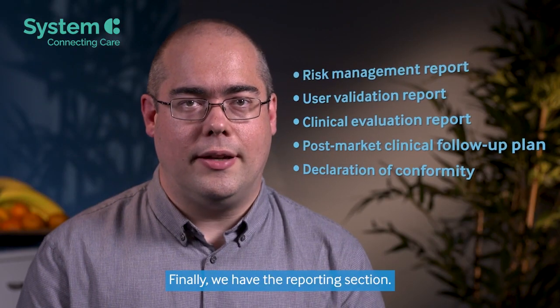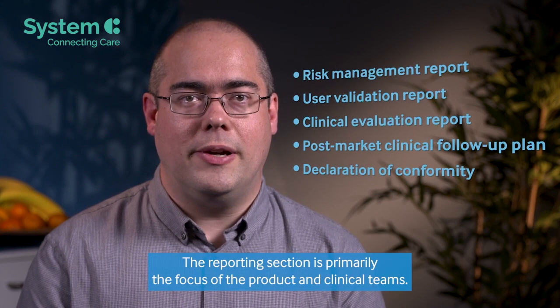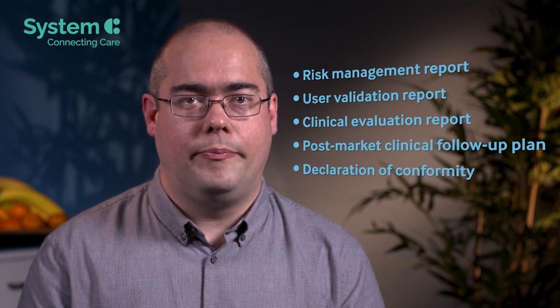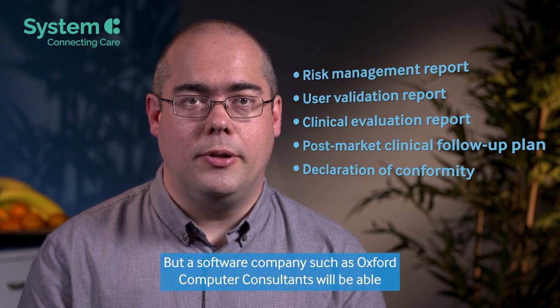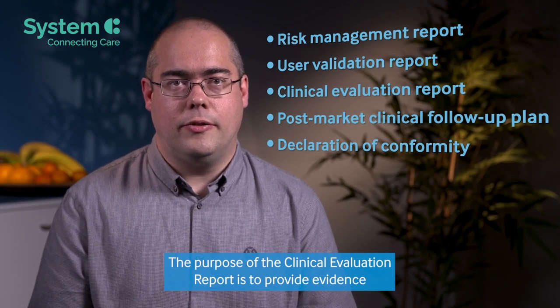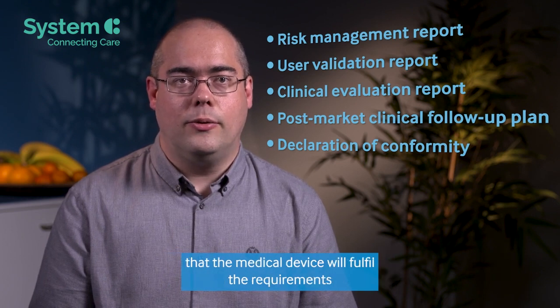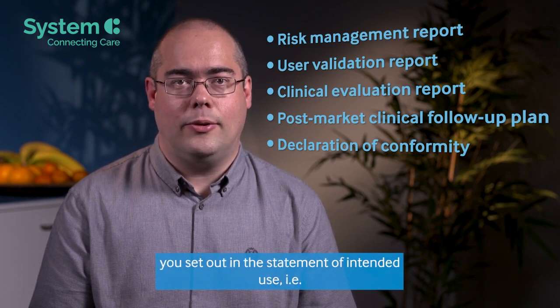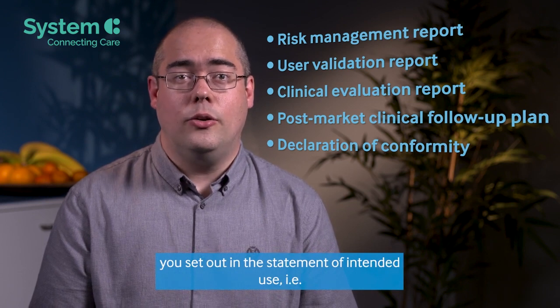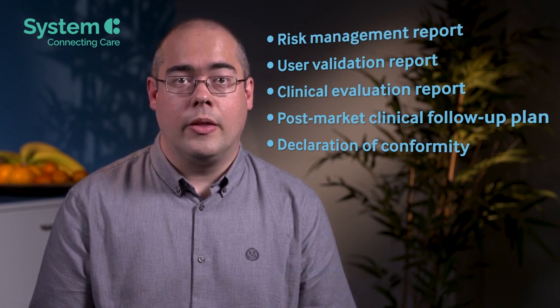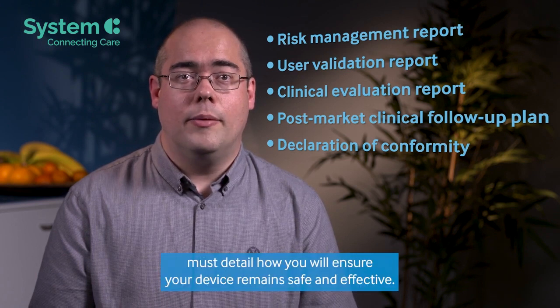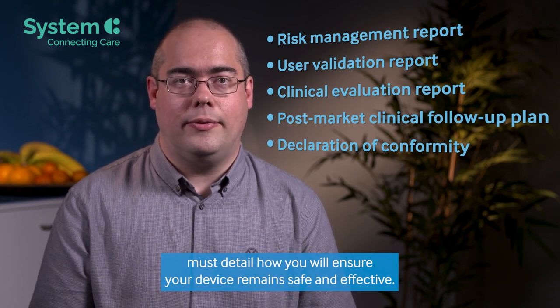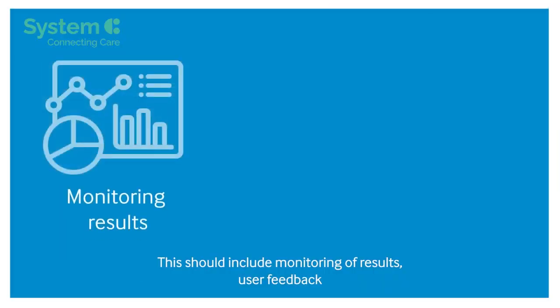Finally, we have the reporting section. The reporting section is primarily the focus of the product and clinical teams. But a software company such as Oxford Computer Consultants will be able to help you with the risk management report and the user validation report. The purpose of the clinical evaluation report is to provide evidence that the medical device will fulfill the requirements you set out in the statement of intended use, i.e., your device does what it says it does. The post-market clinical follow-up plan must detail how you will ensure your device remains safe and effective. This should include monitoring of results, user feedback, and planned software updates.